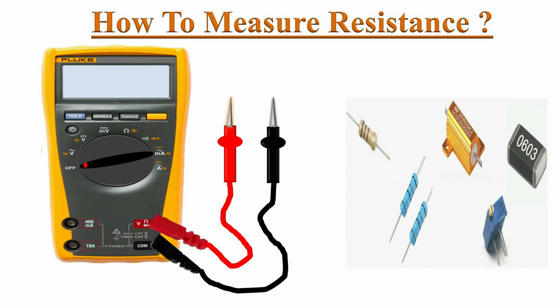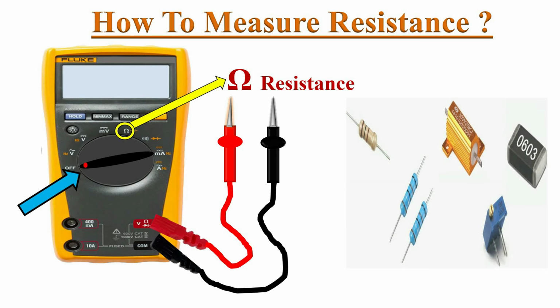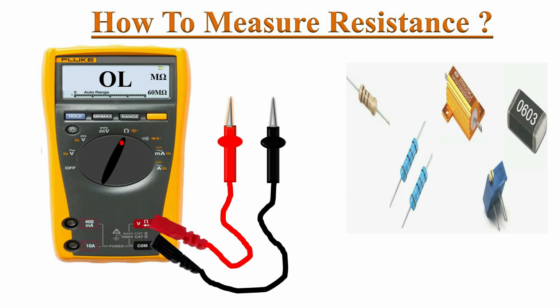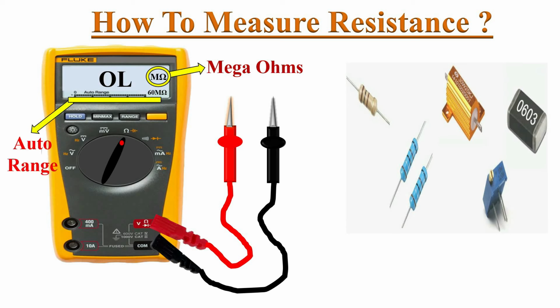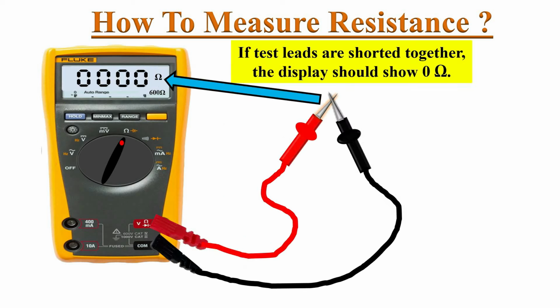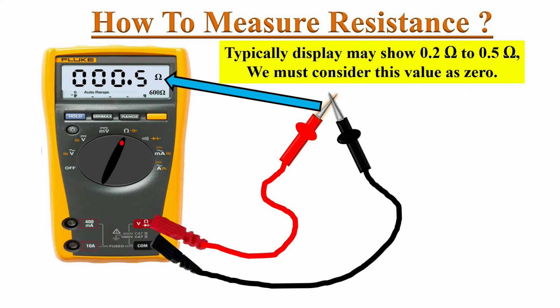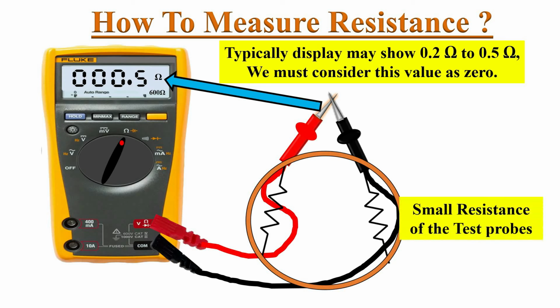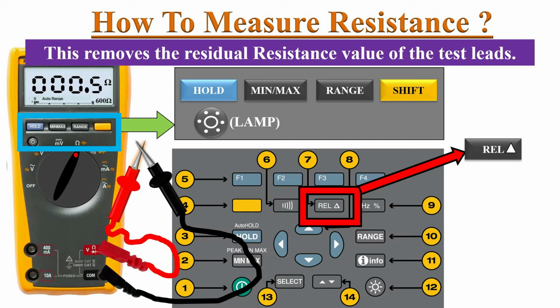Next topic, how to measure resistance with a DMM. Identify this ohm symbol on the dial and just turn the knob to that position. The meter switches on. The mega ohm symbol appears on the screen and the default test range is auto range mode. The display shows OL reading. This is because there is now an open circuit between the test leads. Just short the test leads. Ideally, the meter will show 0 ohms, but practically the meter may read 0.2 ohms to 0.5 ohms. This small resistance is because of the test leads' resistance. We must consider this resistance value as 0. Otherwise, use this relative function to make the display value 0.